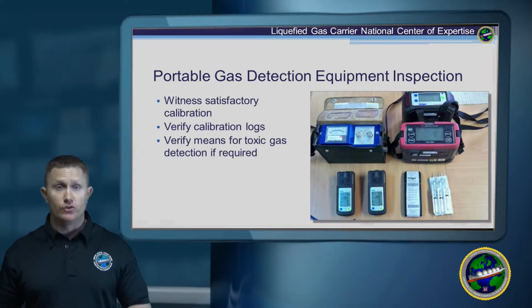This photo shows several different types of portable gas detectors and oxygen analyzers. There are two types of combustible gas detectors that detect hydrocarbons: infrared and catalytic. Always remember, when determining if the proper equipment is on board, that catalytic gas detectors rely on oxygen and therefore cannot be used in atmospheres that are inert to check for gas concentrations.